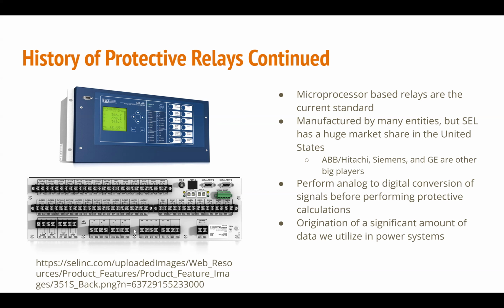With the currents and voltages, we take our signals coming in from the power system and tie them onto these data points or connection points, and this relay has a computer inside of it where it converts these actual values into ones and zeros, and calculates things like: if you have current that goes to this level for this amount of time, then we're going to trip a breaker.